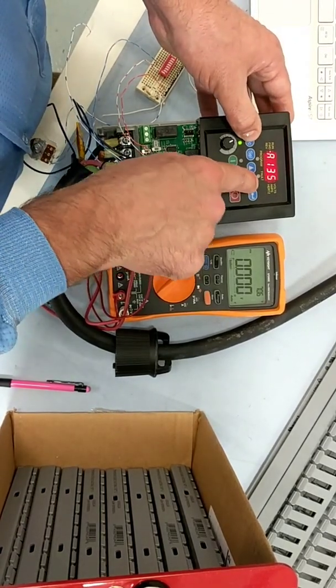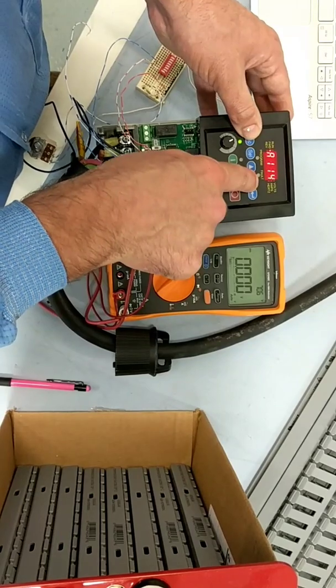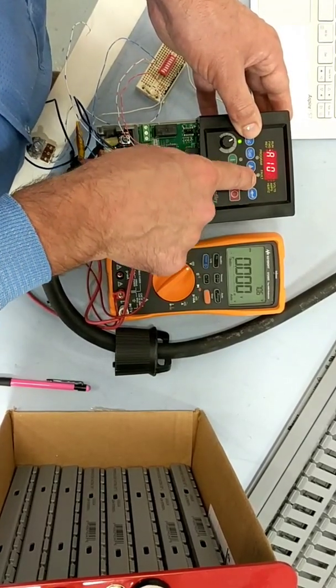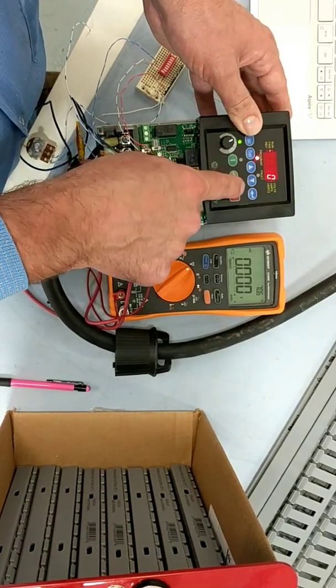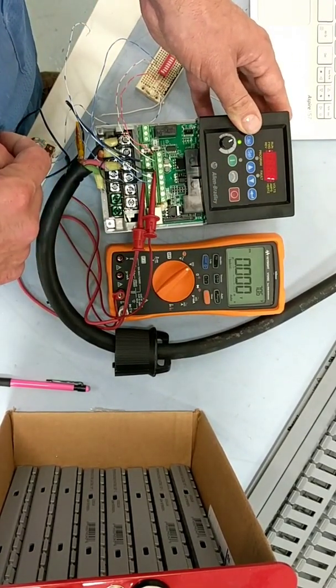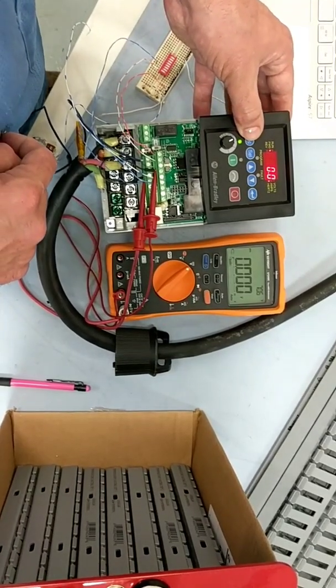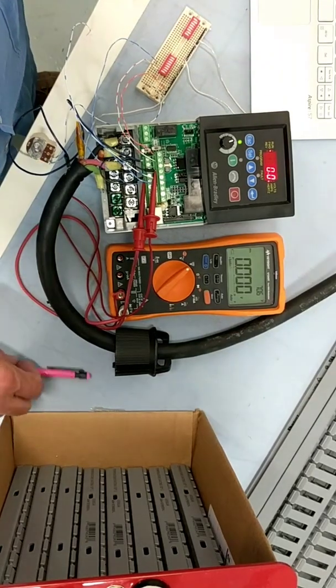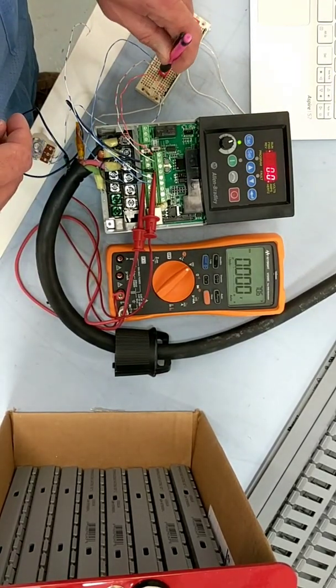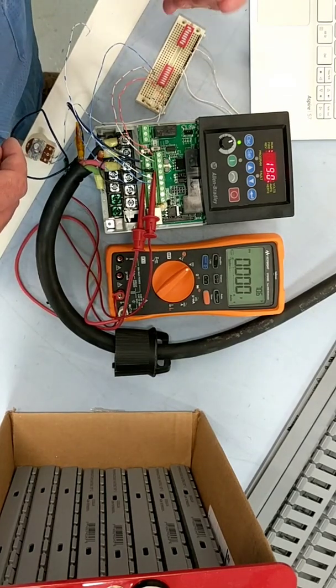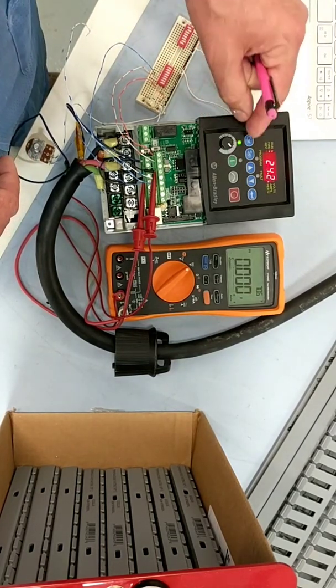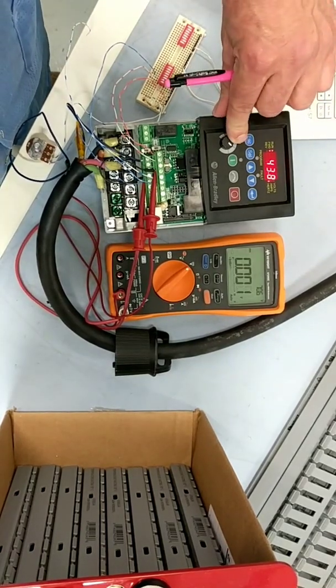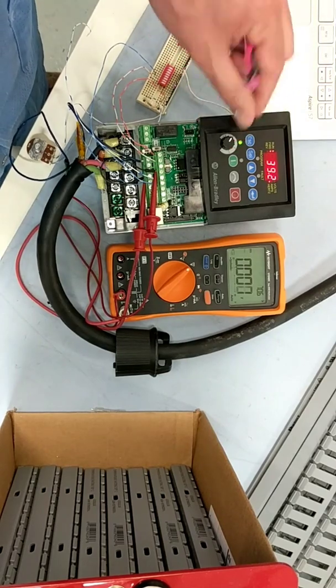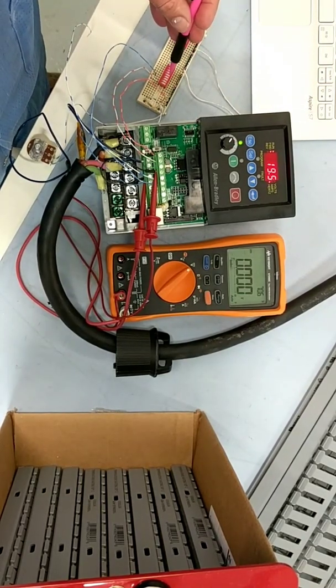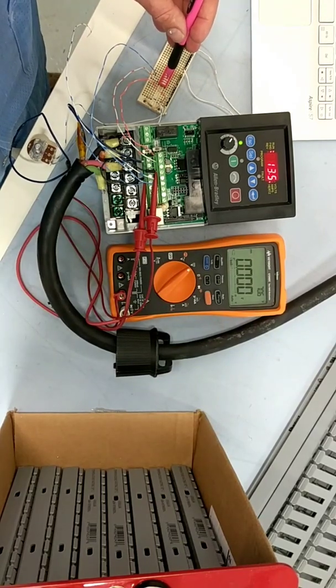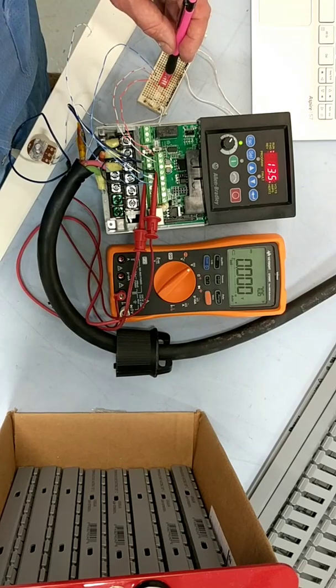And let's go ahead and do the A101 program lock to prevent Todd from tampering with it. Okay, I've hit the start button, and we can see we are controlling it with the pot on the front of the drive, and when we change over to the discrete input number 2, it's going to be controlled by the 4 to 20 input.